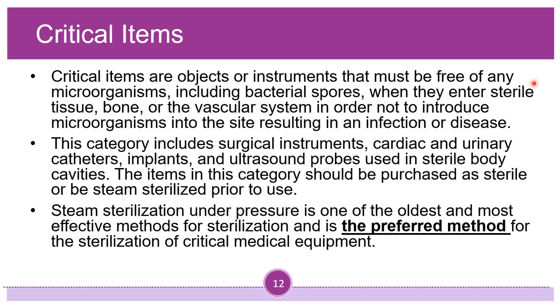So critical item. If the item is heat sensitive and cannot be steam sterilized, the object may be sterilized with ethylene oxide, hydrogen peroxide gas plasma, ozone, vaporized hydrogen peroxide, or liquid chemical sterilants. So liquid chemical sterilants. With the exception of 0.2% peracetic acid, 12 minutes at 50 to 56 degrees Celsius, they have indicated exposure times that range from 3 to 12 hours. So for our liquid chemical sterilants, we're looking at an exposure time of 3 to 12 hours, except for peracetic acid. So that's a pretty long time. That's a pretty long time for a liquid chemical sterilant.